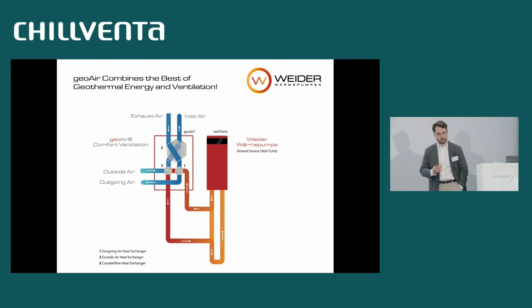The geoAir has 3 heat exchangers. The first one, number 3, is the actual air-to-air heat exchanger, which is quite standard in ventilation systems. And it recovers the heat and the humidity from the exhaust air. But where the innovation comes in is actually the heat exchangers 1 and 2. The first one is a brine to air heat exchanger, and the goal is to win energy from the outgoing air and store it in the source.